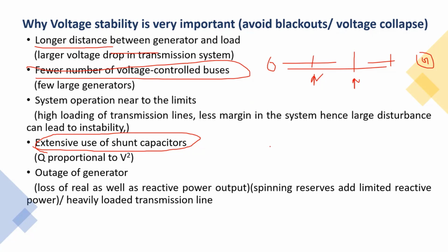Otherwise, what will happen? You are not operating at the optimal unity power factor. The capacitors will be injecting reactive power into the system, resulting in high voltage, first at the distribution level. Then the LV side of the transformer voltage is high and the HV side transformer voltage is low. Reactive power will start flowing from the LV to the HV side, and then goes on. So reactive power from the shunt devices or the lower voltage distribution system will start flowing into the transmission system, and it will increase the transmission voltage also. So this results in a problem percolating: whatever the origin of the problem was at the distribution level, it has extended to the transmission level. That's why proper utilization of shunt capacitors in the system by the operators is very important.